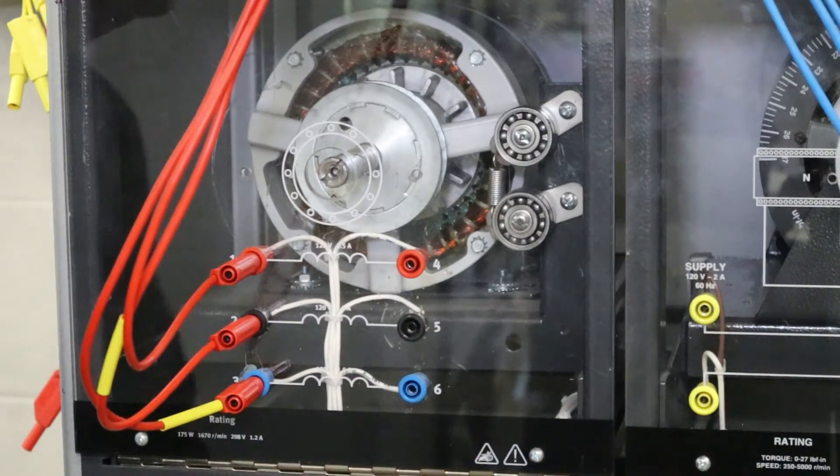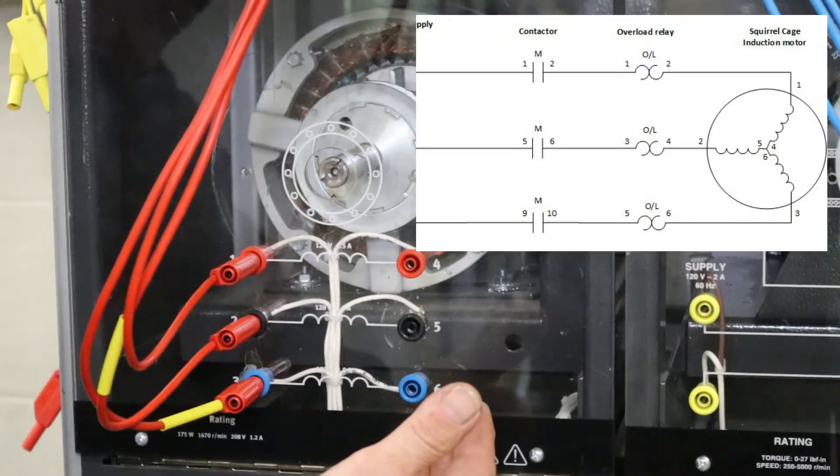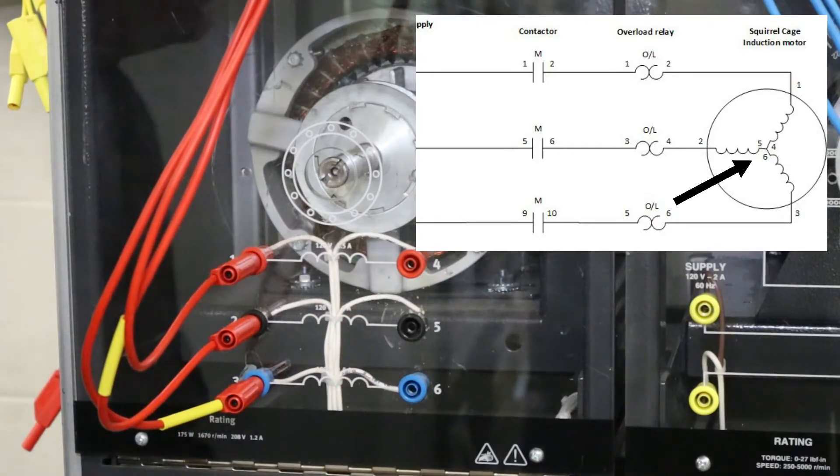If I were to power this up and attempt to operate it, the machine would not turn. According to the diagram, this machine was supposed to be wired in a Y configuration, and terminals four, five, and six had to be connected together.